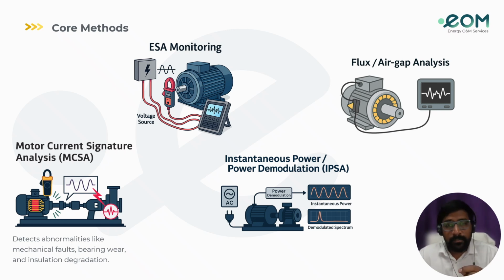And the next one we'll see is flux or air gap analysis, which targets eccentricity and magnetic asymmetries where flux sensing is available. It measures the air gap and magnetic flux, and end winding leakage flux, with a search coil or flux probe placed near the stator slot at the end winding window. Because it directly senses the electromagnetic field, flux analysis is also less sensitive to supply distortion, and rotor and air gap anomalies are cleanly visible.